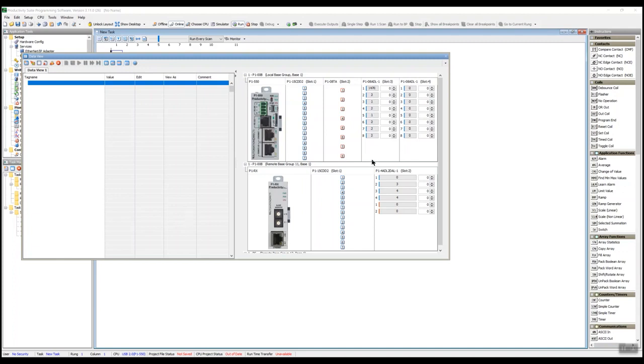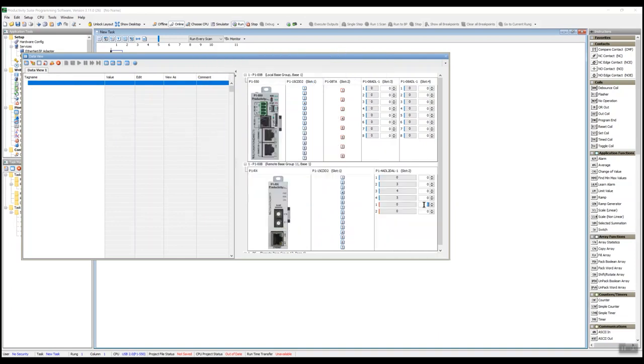To test analog inputs, use a current or voltage simulator and verify the PLC is indicating the expected value. If you don't have a simulator, you can use an analog device of the same signal type and wire it to each terminal one at a time. To test analog outputs, use the PLC programming software to set the output value to a unique level for each channel and use a multimeter in the appropriate mode to verify the expected readings at the terminal block. If any channel doesn't operate as expected, make sure the I/O card has input power and the wiring is correct.